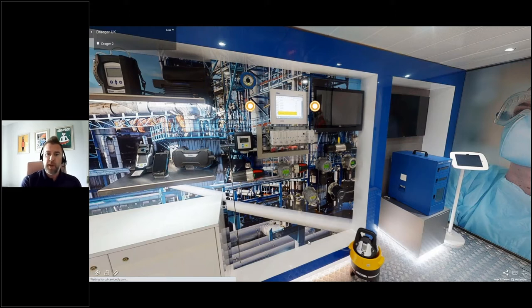So first and foremost, we have the Dräger GS01. This is Dräger's wireless flammable gas detector that's been designed as wireless from the ground up. The GS01 uses a reliable single beam triple wavelength IR source, delivered by a microelectronic mechanical system, or MEMS chip. This ensures lifetime detection stability with no need for recalibration, also coupled with ultra low power consumption of just 5 milliwatts. This also allows for a battery life of 2 years. The same battery is exchanged in the field by means of an EX enclosure, so it really lends itself to a long life, maintenance free wireless gas detector with a huge amount of flexibility.